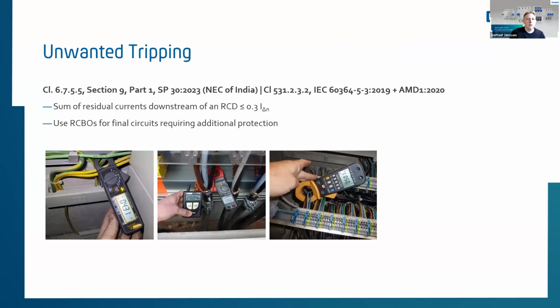Yeah, another topic is how to prevent unwanted trippings. The sum of residual currents downstream of an RCD should not exceed 0.3 times I delta n, so the rated residual current of the breaker. And we have already shown here a small possibility of how this can be prevented: use RCBOs for the final circuits to split up the final circuits. If you look at the pictures here, for example at the protective conductor, you have different small loads on it, and in the end those loads would sum up and would bring an RCD to its tripping threshold. Krish already explained this a bit in his text. If you install one RCD for a whole house, this will give you troubles afterwards.